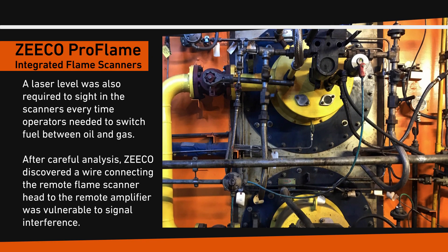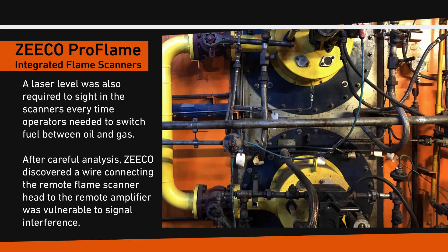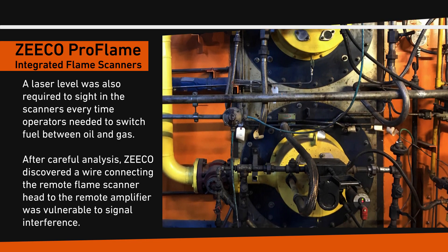A laser level was also required to sight in the scanners every time operators needed to switch fuel between oil and gas. After careful analysis, ZEECO discovered a wire connecting the remote flame scanner head to the remote amplifier was vulnerable to signal interference.